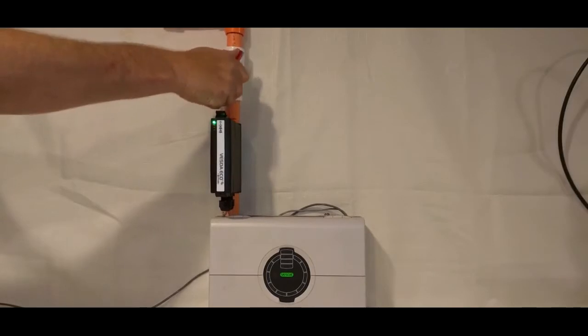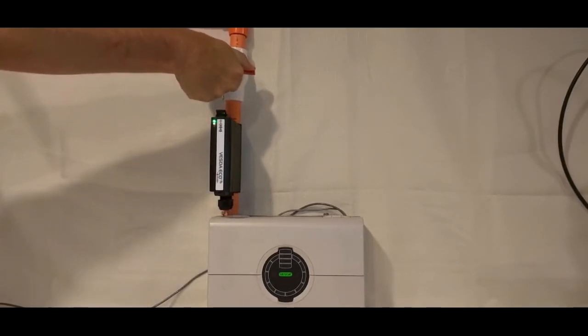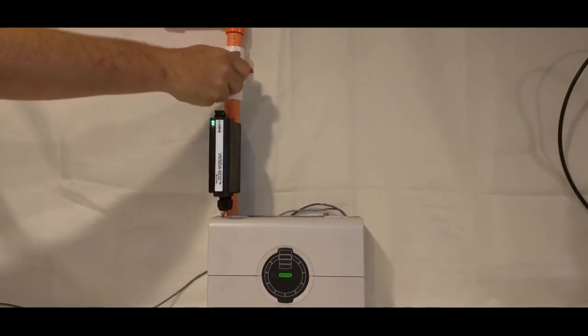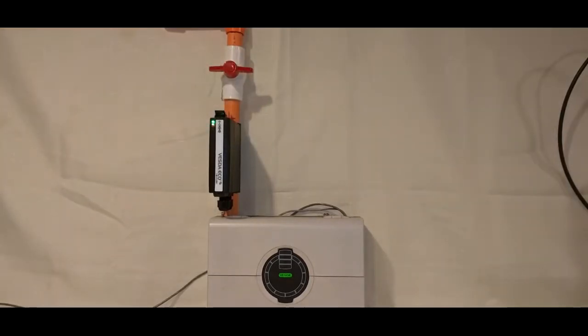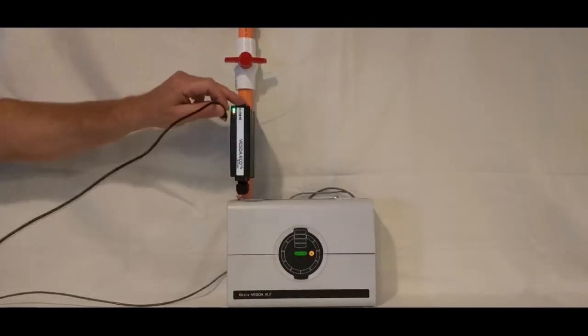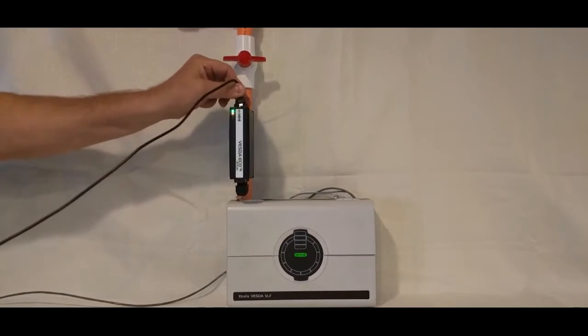Next, close the ball valve above the ECO. If there is no ball valve, you must install one. This prevents external air from diluting the calibration gas. Now, connect the mini USB to the ECO.